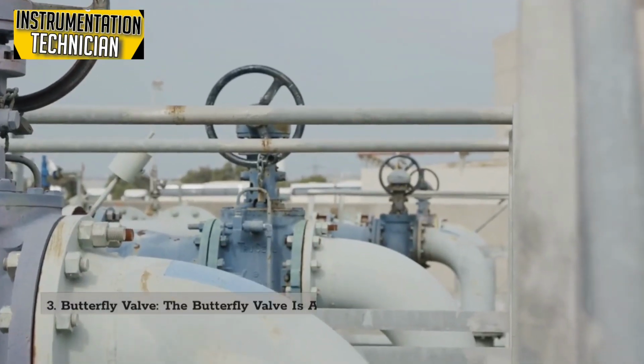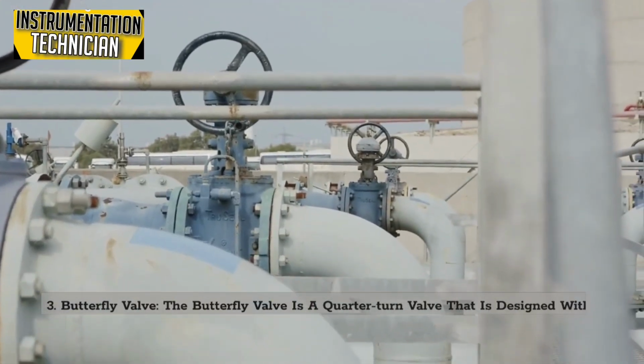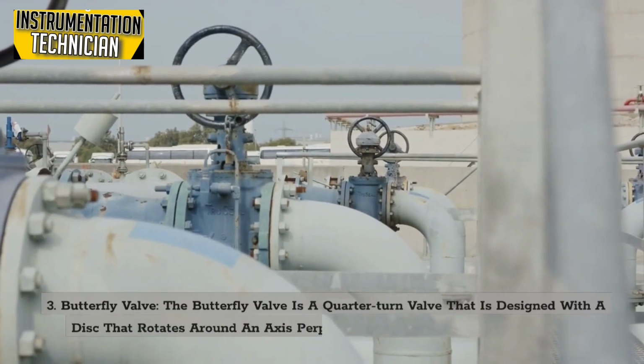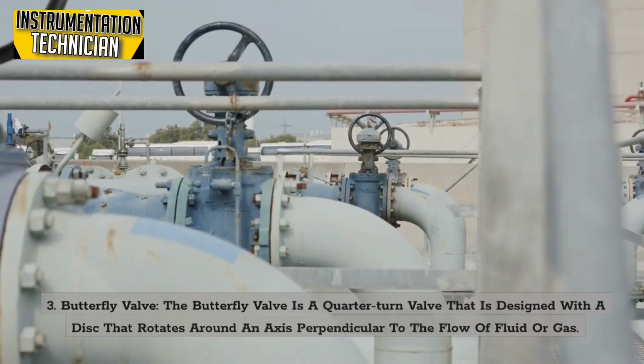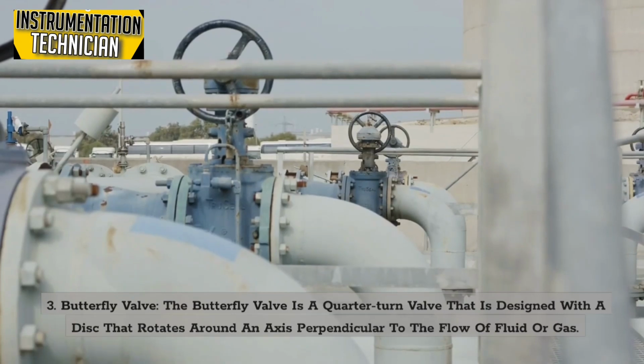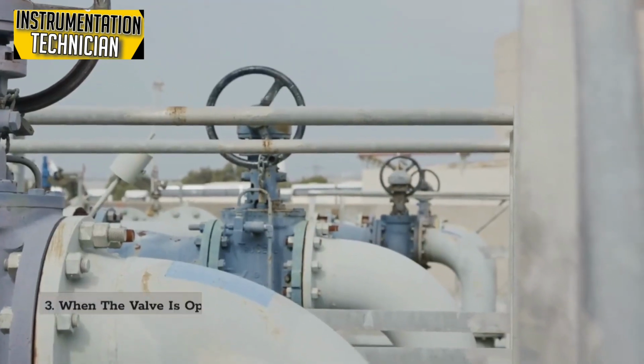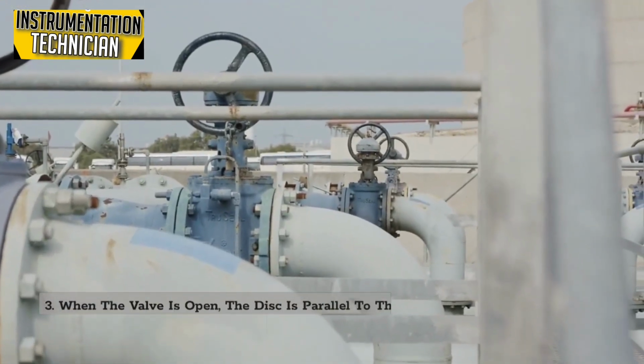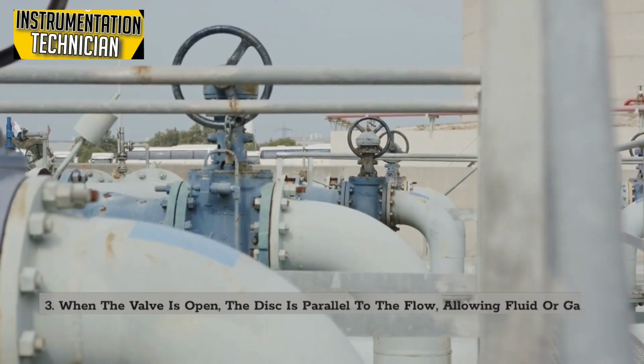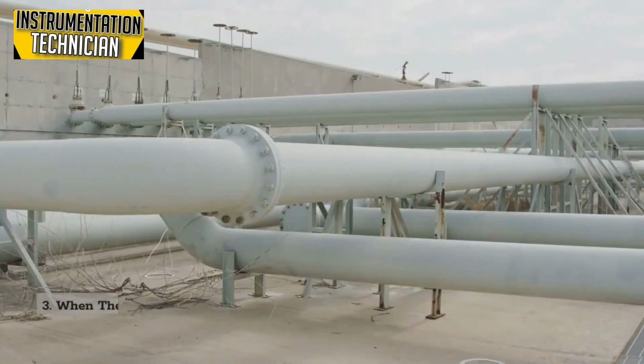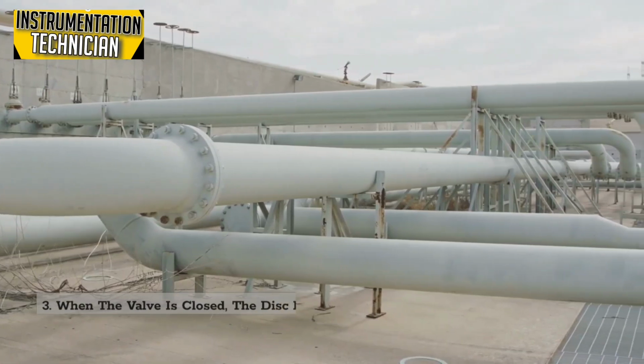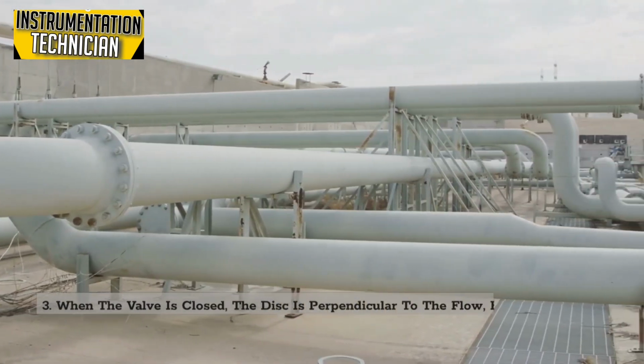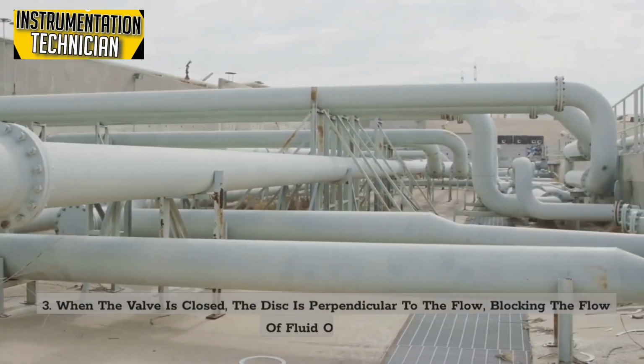Butterfly valve. The butterfly valve is a quarter-turn valve that is designed with a disc that rotates around an axis perpendicular to the flow of fluid or gas. When the valve is open, the disc is parallel to the flow, allowing fluid or gas to pass through. When the valve is closed, the disc is perpendicular to the flow, blocking the flow of fluid or gas.